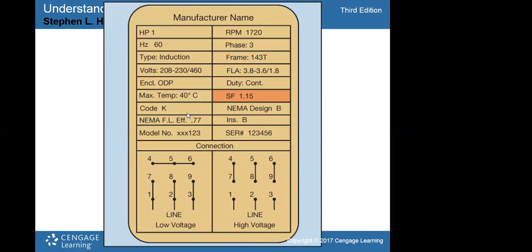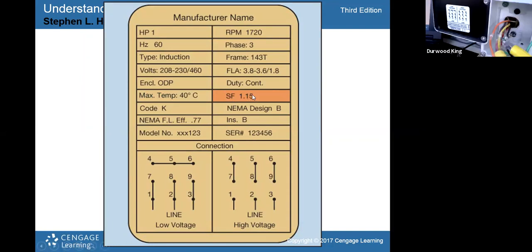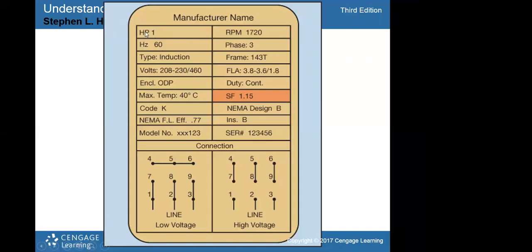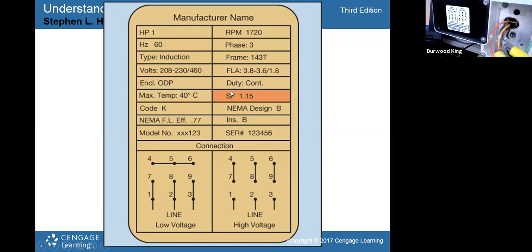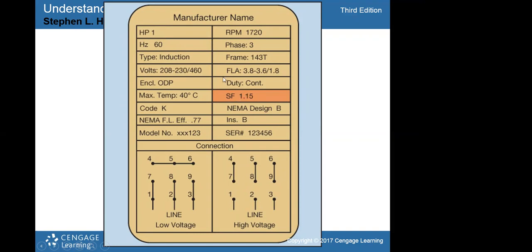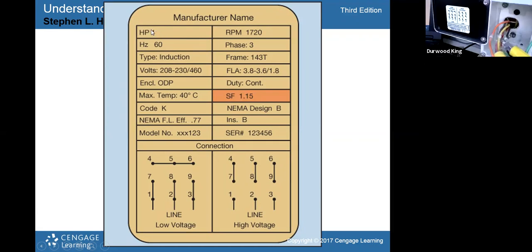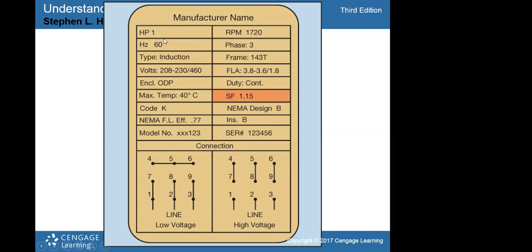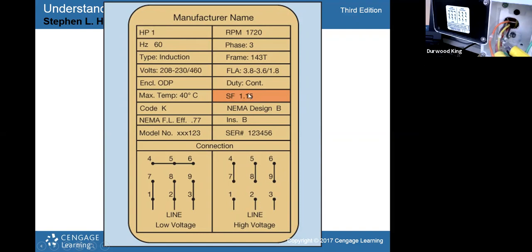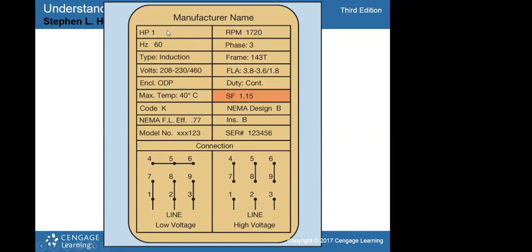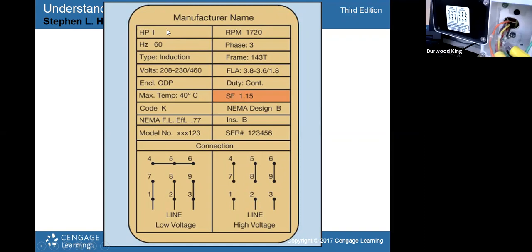Service factor tells you that you multiply that number times horsepower. This motor is rated at 1 horsepower. But if you multiply the service factor times the horsepower, the motor could actually deliver 1.15 horsepower if it got in a strain. So whatever the service factor is, you multiply it times the horsepower. It gives you the true horsepower the motor could deliver without being damaged.